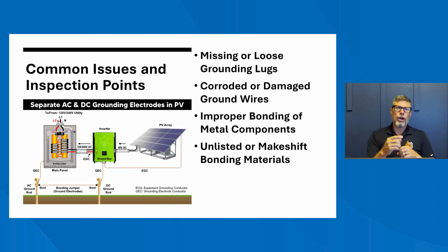If you see a bond wire going from panel to panel or module to module, or if you see gaps in them, you want to make sure there are no rubber grommets in there, because sometimes they do that for spacing. If you do see the rubber grommets, you want to see that bond wire go from one side to the other, just like we would if we were looking at a water filtration system. You want to see the bond wire jumping from copper line to copper line, because that plastic doesn't conduct electricity.